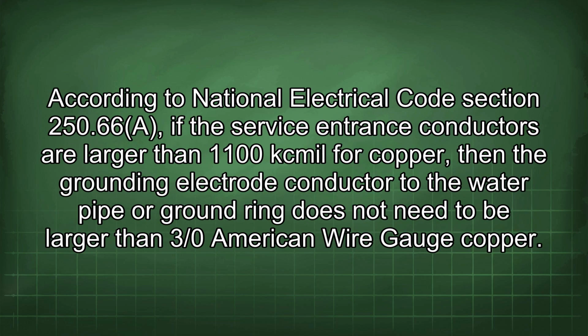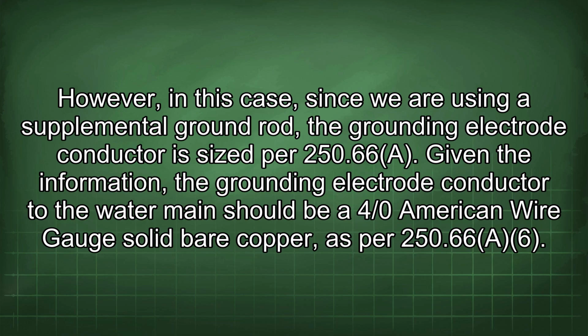250.66. According to National Electrical Code Section 250.66a, if the service entrance conductors are larger than 1100 kcmil for copper, then the grounding electrode conductor to the water pipe or ground ring does not need to be larger than 3/0 American wire gauge copper. However, in this case, since we are using a supplemental ground rod, the grounding electrode conductor is sized per 250.66a.